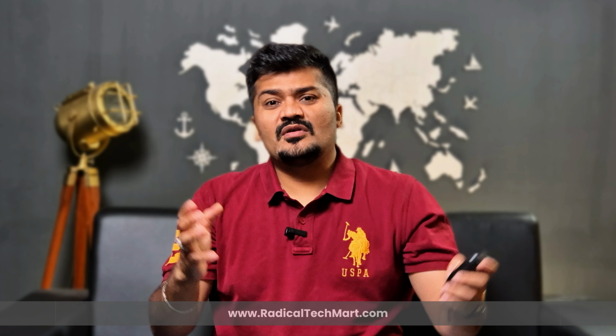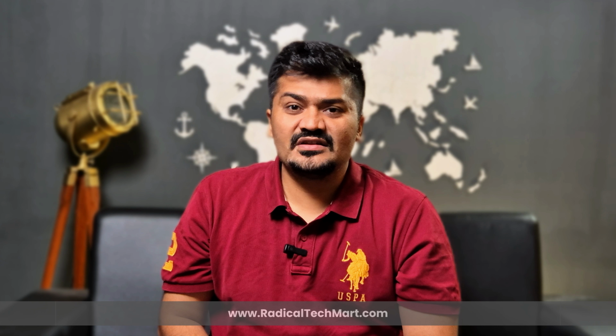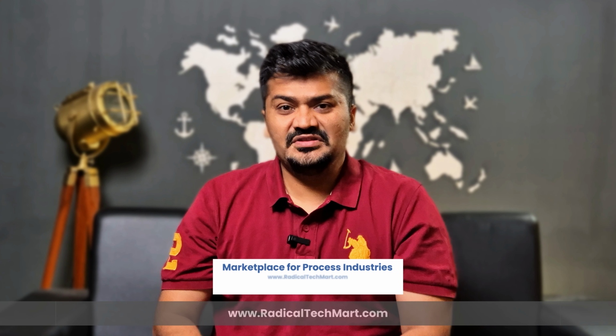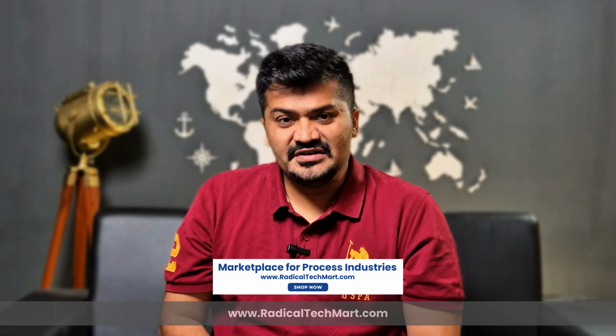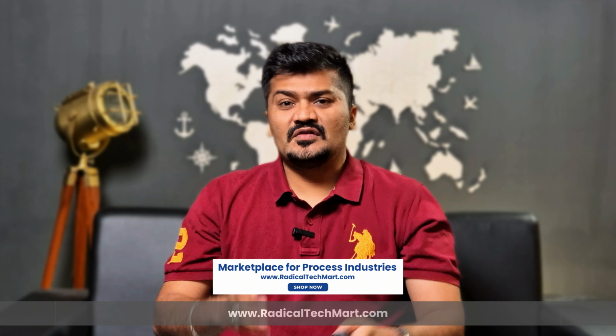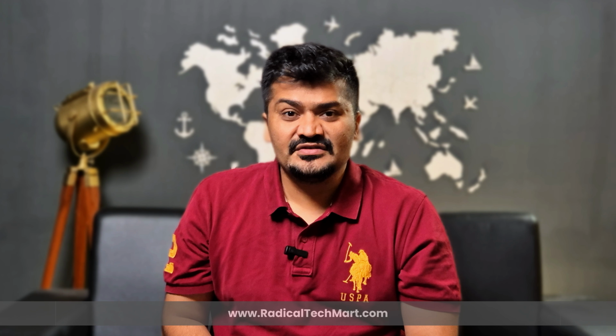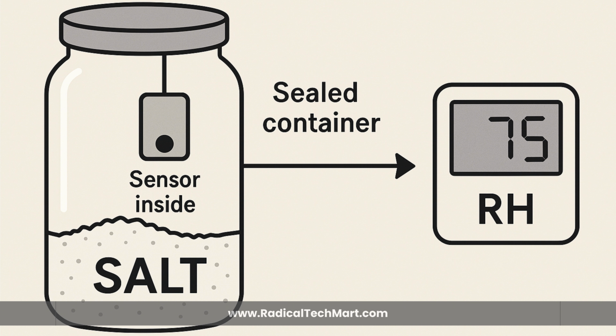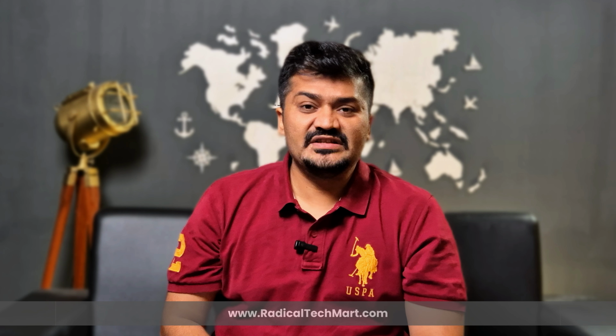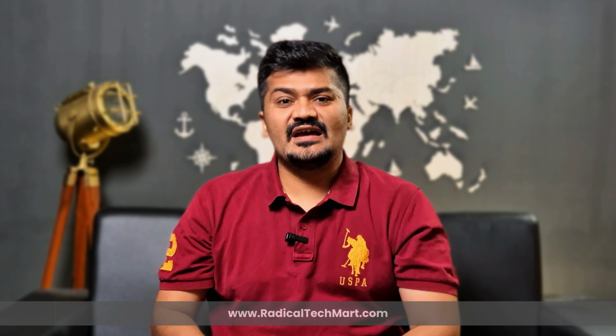Now let's cover in-house versus external calibration. First, let's start with in-house calibration field check. Use a salt solution with known RH points, like NaCl equal to 75% RH. Place the sensor in a sealed chamber with the salt mix. Compare readings and adjust if needed. It is ideal for routine checks or low-risk applications.